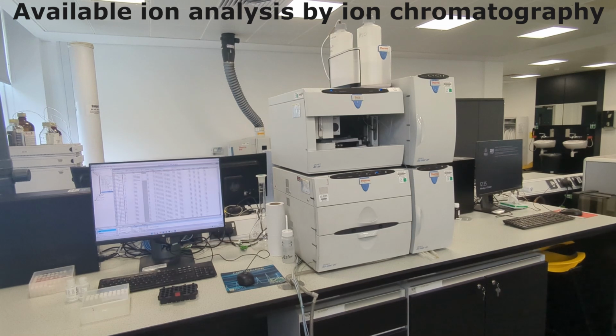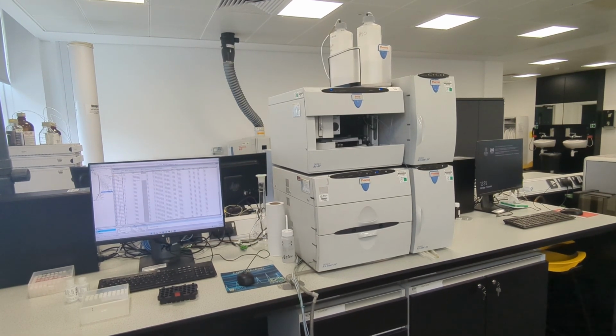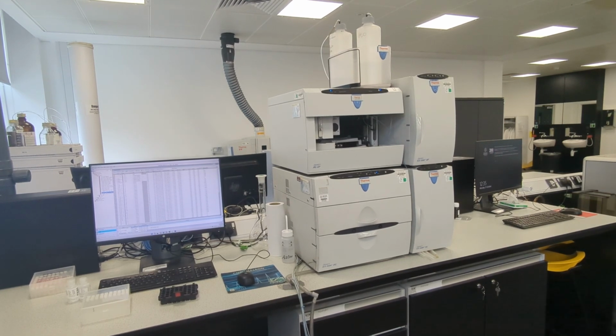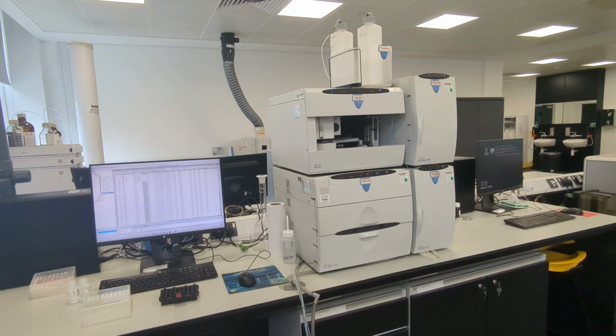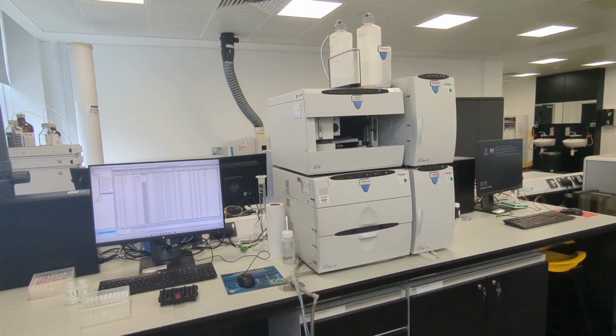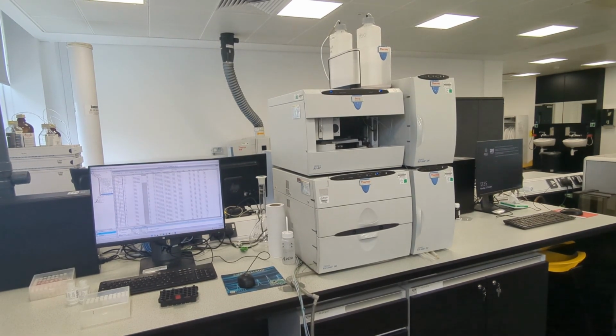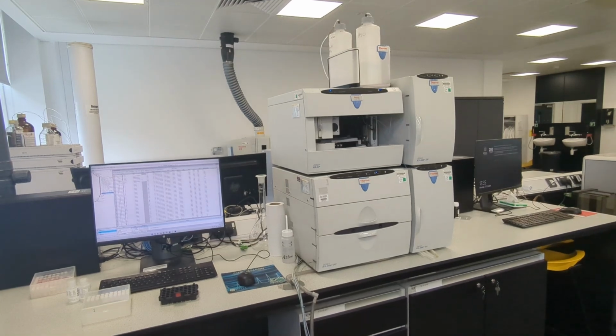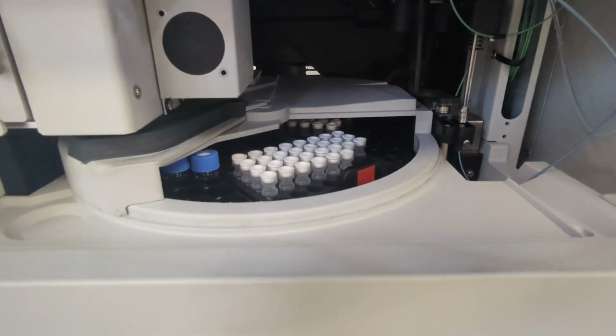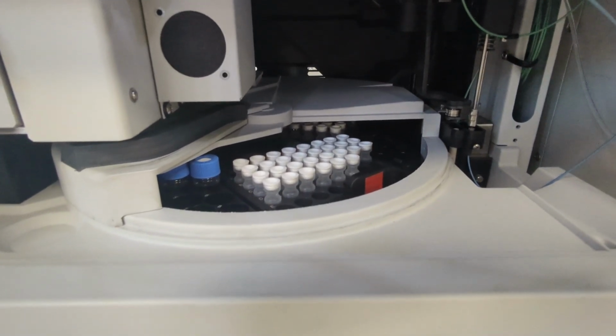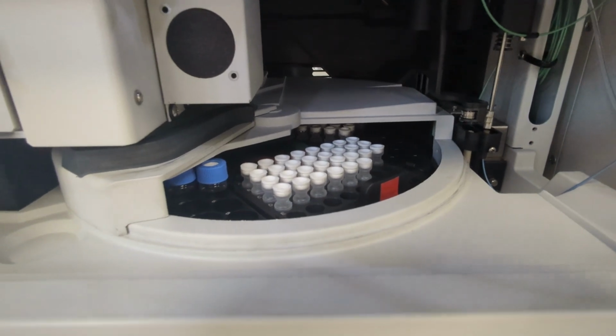This is the Thermo Scientific ICS 5000 Plus ion chromatograph. The instrument contains two parallel systems for analysis of anions and cations. The two bottles on top of the instrument contain the mobile phase, which is used to carry the sample around the instrument. Our filtered samples have now been loaded into the instrument auto-sampler, ready for analysis.